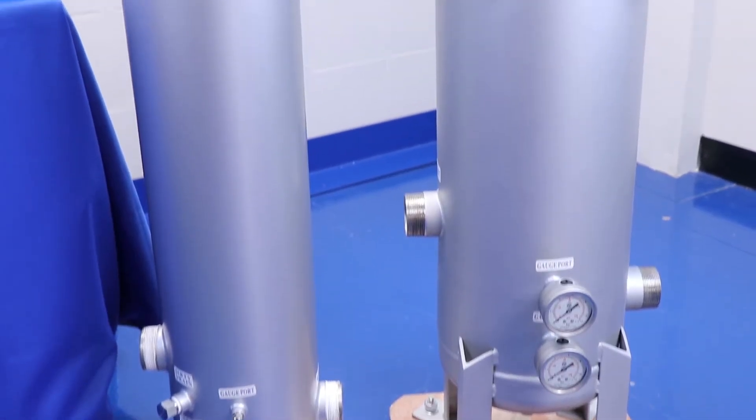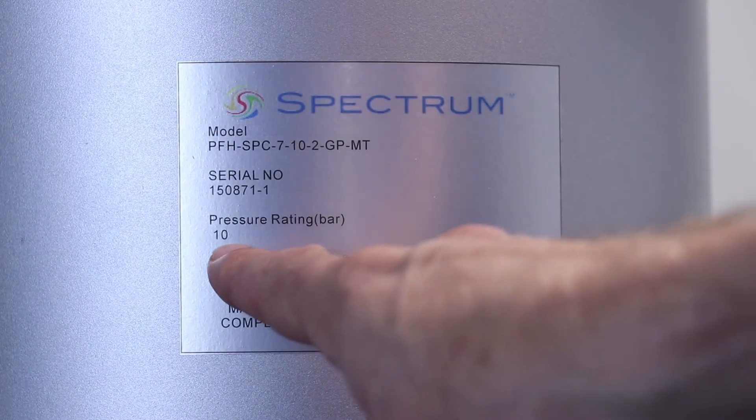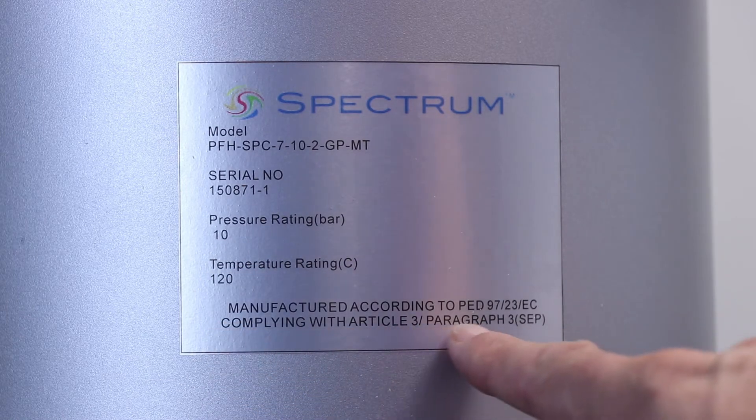Both housings are constructed from 316 stainless steel and are pressure tested to 10 bar or 145 psi. All come DWI certified and PED 97/23/EC compliant, giving peace of mind when dealing with applications from pure water filtration to effluent treatment.